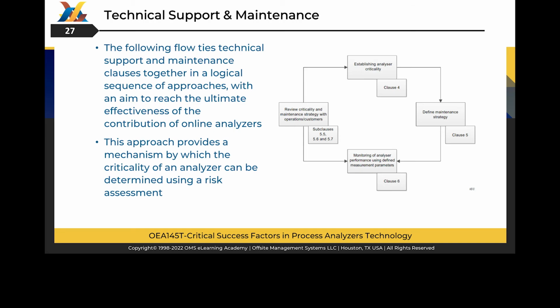The ultimate effectiveness of the contribution of online analyzers is measured by the ability to perform their functional requirements upon demand. Once the functional requirements are identified, the following clauses shall be established to give guidance in achieving the solutions, with the aim of maximizing performance and benefit of installed analyzers, achieving complete operator confidence in the use of online analyzers, ensuring that the analyzer output data is becoming reliable enough to be used by operators, control systems, and other users to improve plant operation, and measuring KPI for the performance and ROI of the analyzer system. This well-established methodology optimizes analyzer performance targets by balancing maintenance costs and benefiting the process.